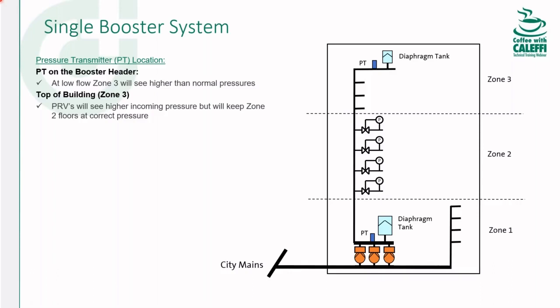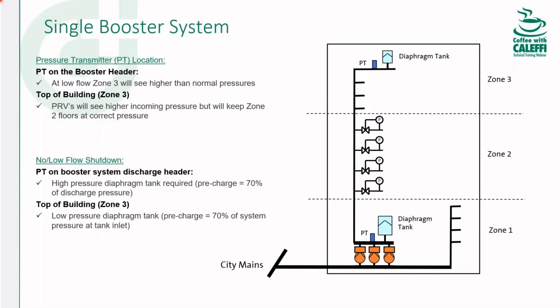So Reece, what can you tell us about pressure transducers and diaphragm tank placements? A lot of times this is designer choice. It's very typical to put the sensor on the discharge header of the system and then have your tank there and just maintain constant delivery pressure. However, when the buildings get really tall, you're working with a much higher working pressure at the bottom to deliver the water all the way up to the top. So some designers will choose to put the diaphragm tank up there because then it can be exposed to much lower pressure. And then some will actually put the transmitter up there as well to maintain pressure at the top level instead of the base level with the pumps. And both will work okay.